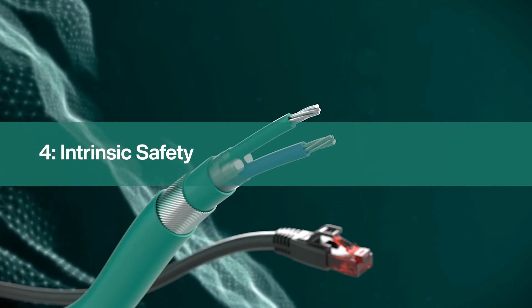2-WISE is short for 2-wire intrinsically safe Ethernet, a definition within the IEC standard for explosion protection. 2-WISE defines interoperability, prescribing limits to values for the electrical circuit. Like FISCO, the fieldbus intrinsically safe concept, 2-WISE prescribes simple planning and validation rules without calculations. As a matter of fact, some of the people that contributed to the 2-WISE standard were also involved when FISCO was standardized about 25 years ago.